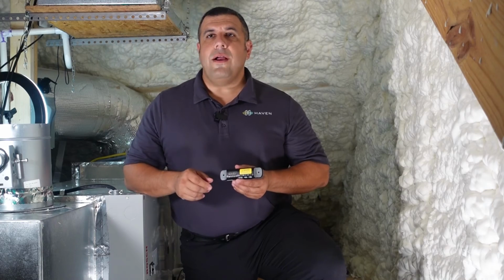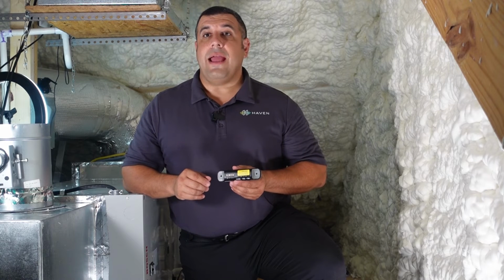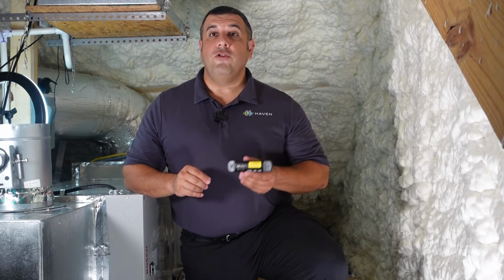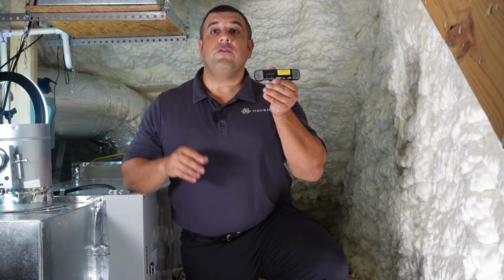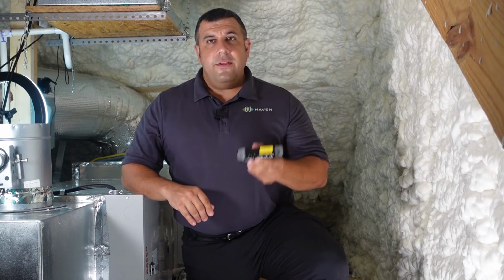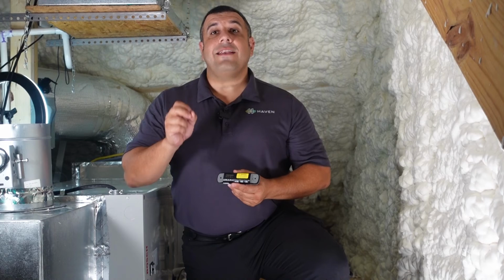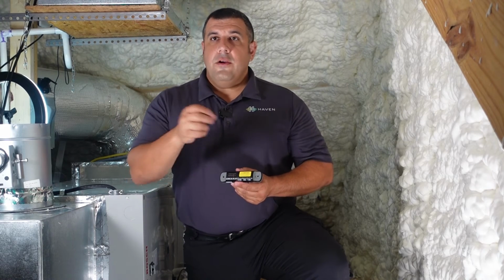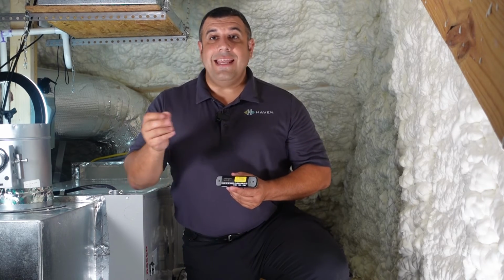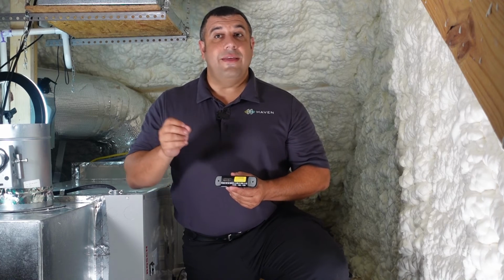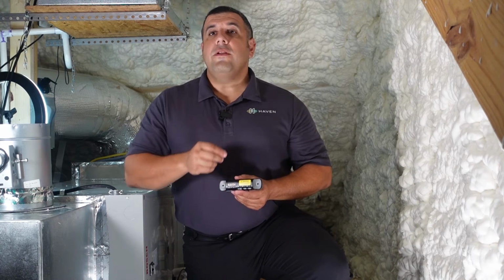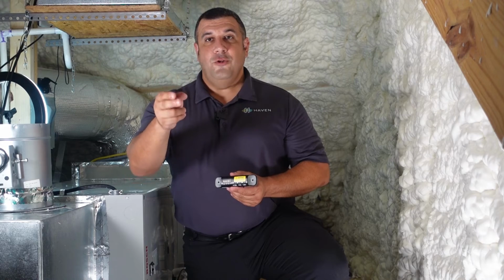The monitor requires airflow to sample the home's air accurately, so connecting a Haven controller to activate the air handler's blower fan is recommended. This will allow you to set regular activation intervals throughout the day. Your customer will also be able to edit that circulation schedule later via the app if desired. The controller install video guide will be linked in the notes below.